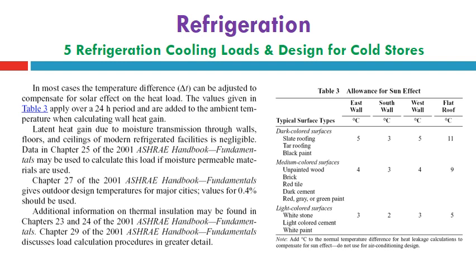In most cases, the temperature difference delta T can be adjusted to compensate for the solar effect on the heat load if compared with the northern side or northern wall, which is in the upper part of the earth. The sun rays cannot reach the northern wall if compared with the east or west or south or flat roof. So this slide will present the allowance of sun effect as shown in Table 3.